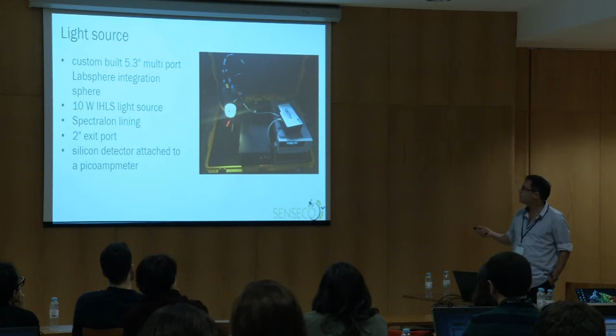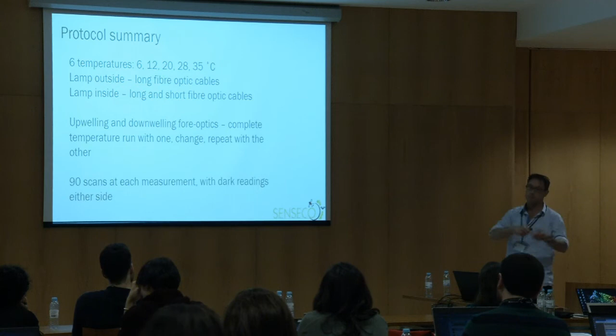All right. Of course, the QE Pro has a temperature controlled detector at around, in my system, -9.8 degrees, but this does increase slightly, at less than a thousandth of a degree, with the increase in the ambient air temperature. Okay, independent of the sort of configuration, but it does. There's a slight change in detector temperature with the change in air temperature.